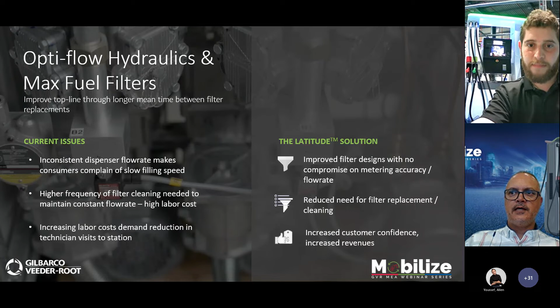The dispenser flow rate is either inconsistent, or it starts off at maximum flow rate and then in a short space of time starts reducing to a slow flow. This is mainly caused by the quality of the fuel, the service station itself, or the tanks having debris. There could be debris in the product that causes the filters to clog up, which ultimately slows down dispensing. Slow dispensing frustrates the customer purchasing the fuel, who wonders why it's taking so long to put 30 liters in their car.